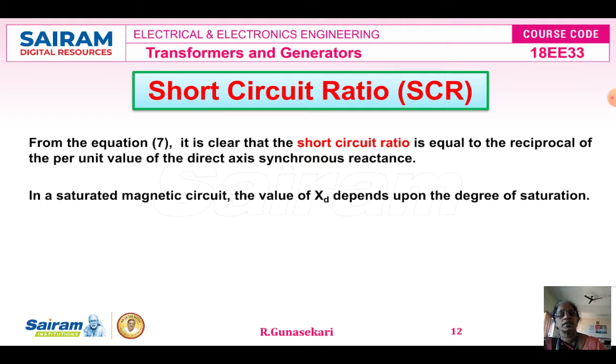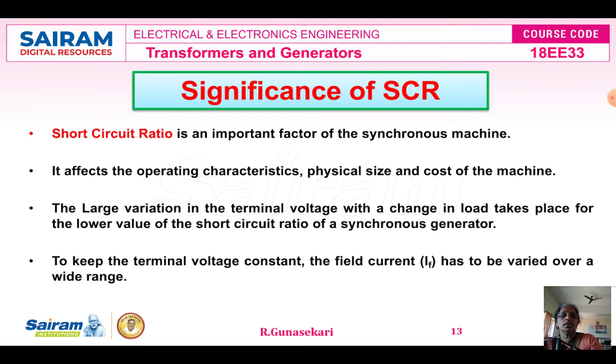But in the saturated magnetic circuit, the value of the direct axis synchronous reactance XD only depends upon the degree of saturation. That's why this is called the saturated reactance. Now, what is the significance of the SCR? This is very important. The short circuit ratio is an important factor in the synchronous machine, either motor or generator. The SCR affects the operating characteristics, physical size and the cost of the synchronous machine.